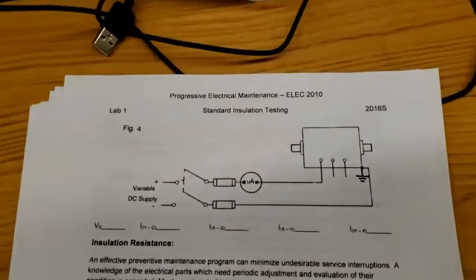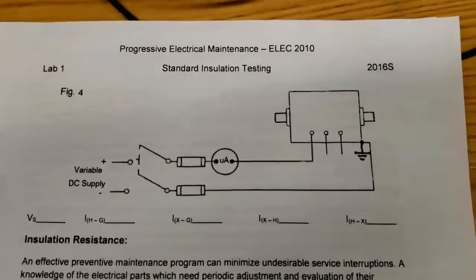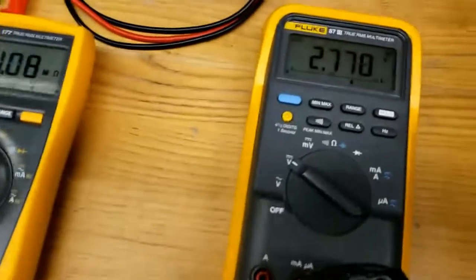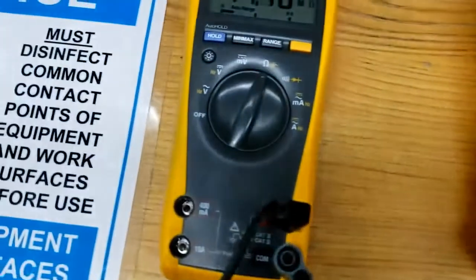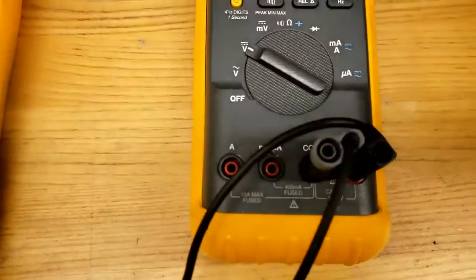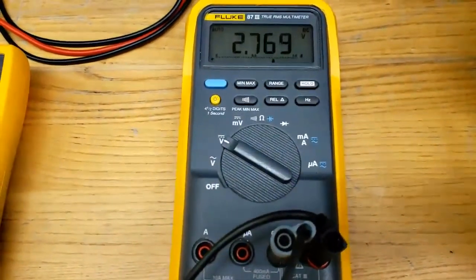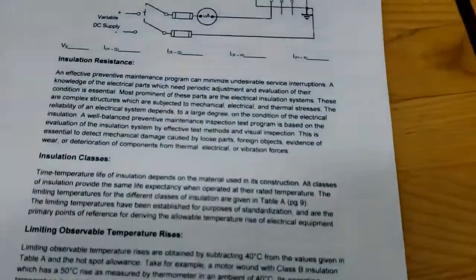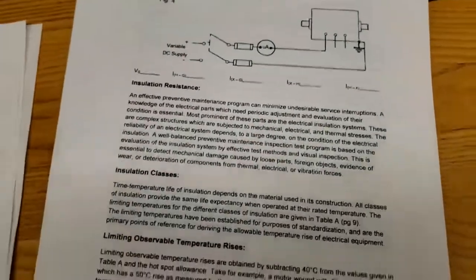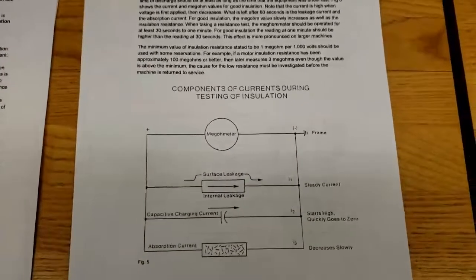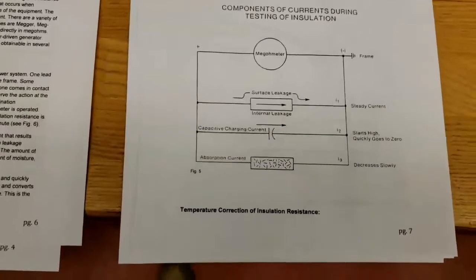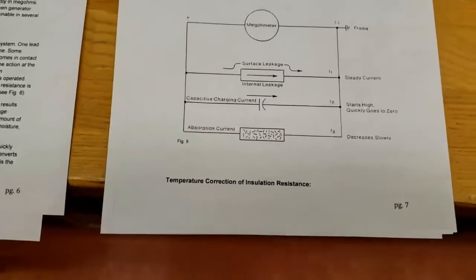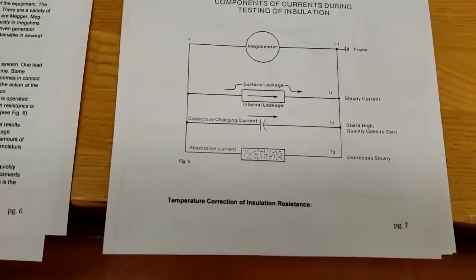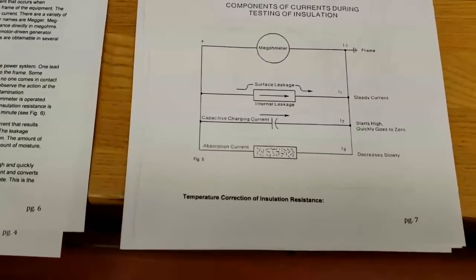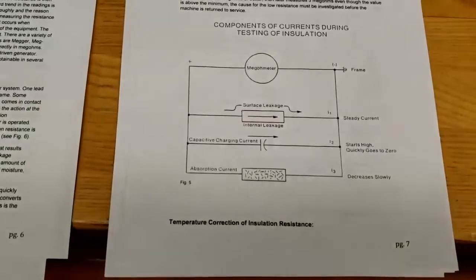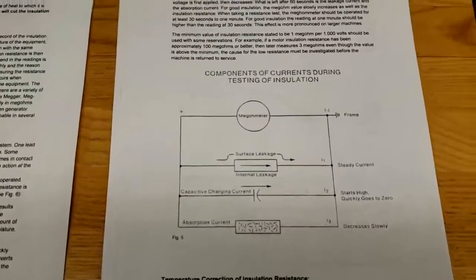And then same thing, I'm going to put 100 volts, just put a microammeter in there. Some of these meters will do microammeter. This one will. The 177s will not. So you have to get one of the 87s before you can get your microamps and milliamp settings. Okay, so the three methods, and then read through the rest of the lab and take the readings in sequence. There's a section in the lab here on the components of currents during testing of insulation, and it explains it as to why. You get a capacitive effect, you get surface leakage, you get internal leakage, and you get absorption current, which slowly decreases. So read up on that. The lab sheet's got good information. Read the entire thing.